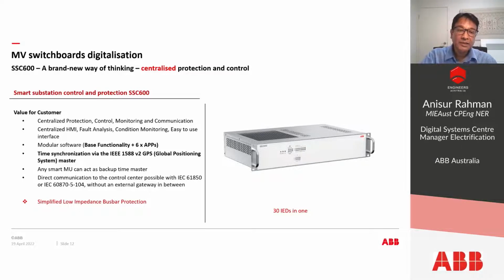In addition to that, it has other benefits as well. As I mentioned, the modular software has base functionality with current, voltage, and frequency base. And in addition to that, it has 6 apps, whatever protection you need. And it has time synchronization via IEC 1588 and PTP time synchronization, so that you don't need any additional GPS. Also, it can communicate directly to the SCADA or control center by IEC 61850 or IEC 60870-5-104 without any external gateway in between. So there is no gateway required.